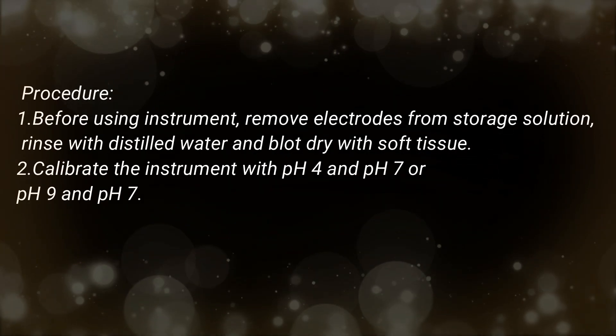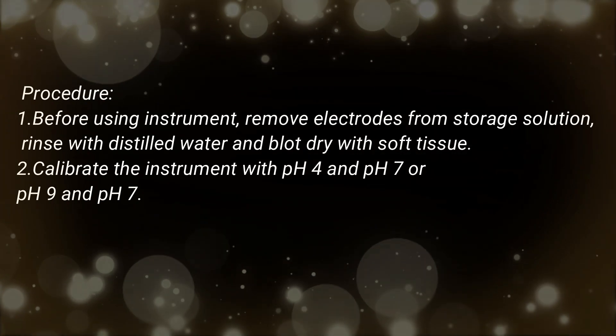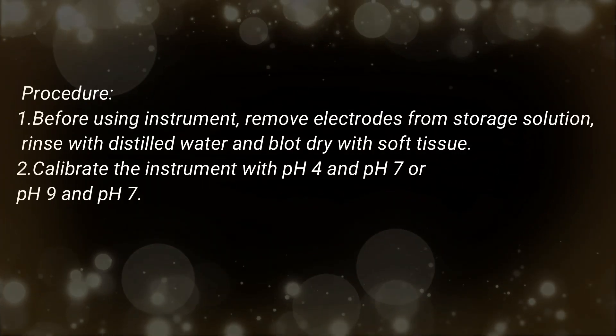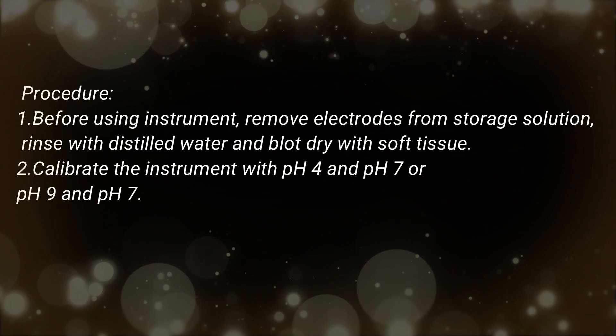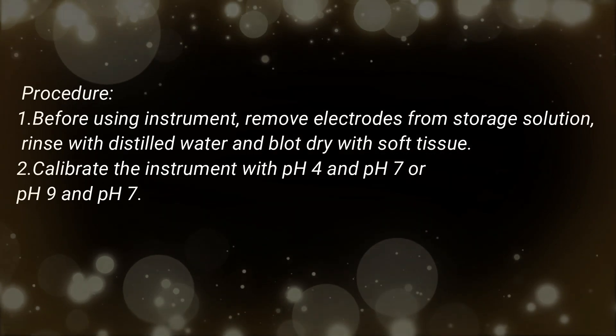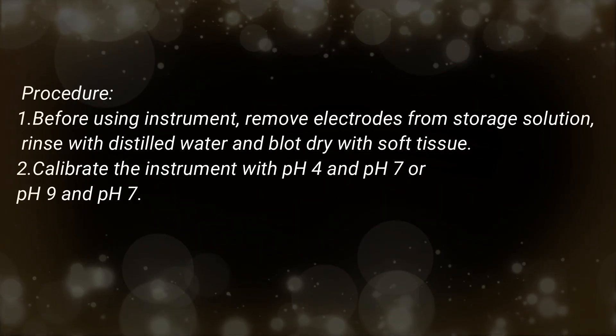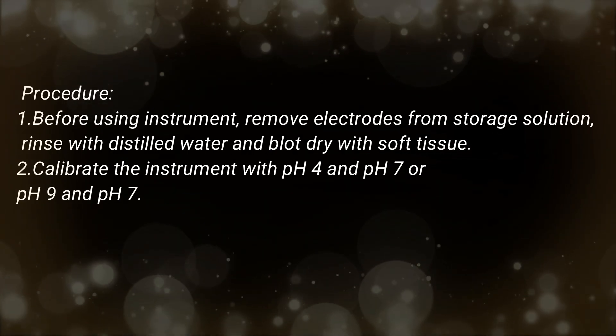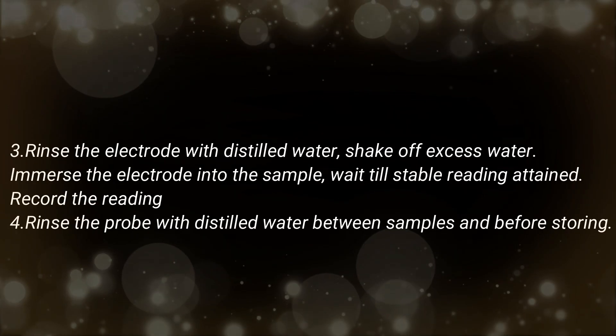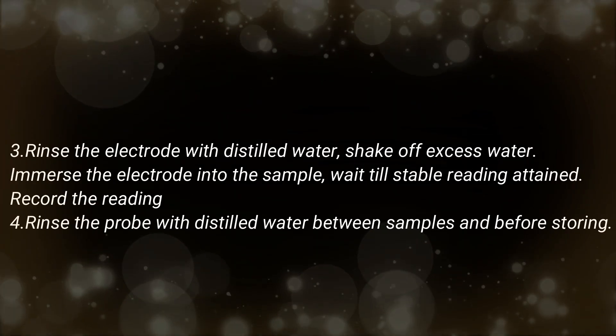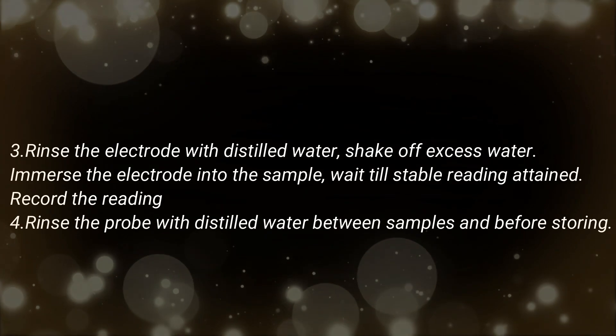Before using the instrument, remove the electrodes from the storage solution. Rinse with distilled water and blot dry with a soft tissue. Calibrate the instrument with pH 4 and pH 7, or pH 9 and pH 7. Rinse the electrode with distilled water and shake off excess water.